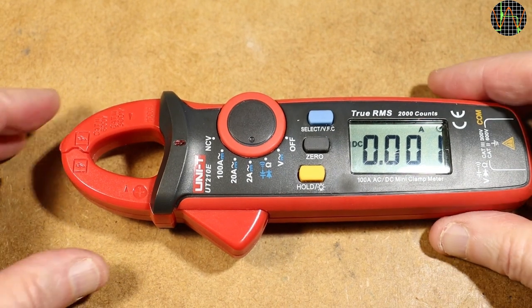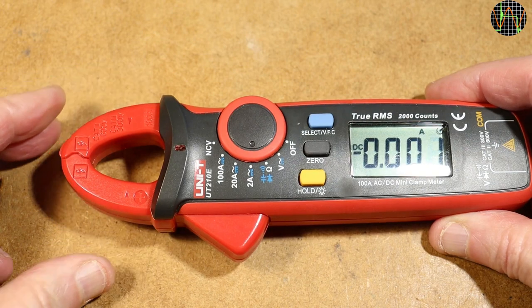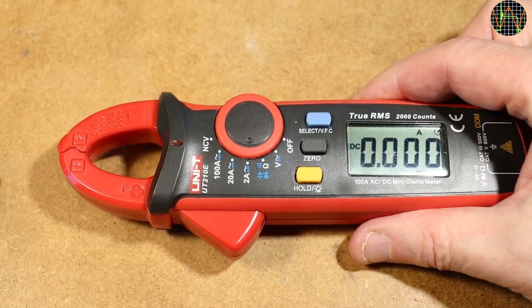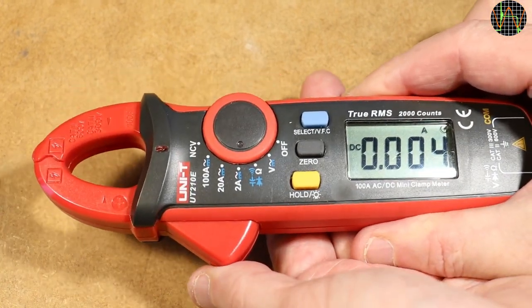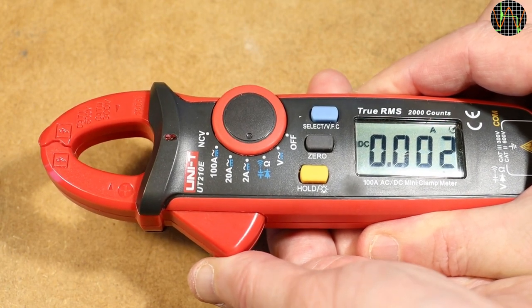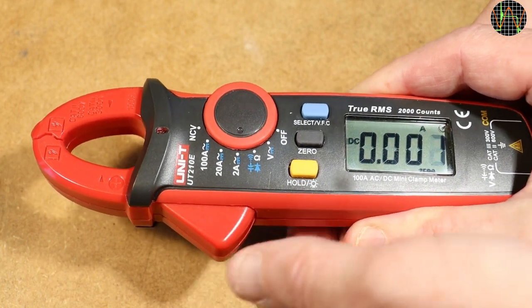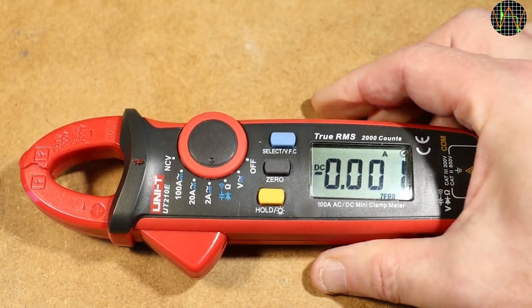The clamp itself is quite sensitive to touch because it can easily cause tiny changes in the width of the air gaps. Needless to say, it has to close properly to begin with or all your measurements are invalid anyway, but as a rule, don't touch anything with the clamp or force it into a bunch of cables and never hold the meter by the clamp.